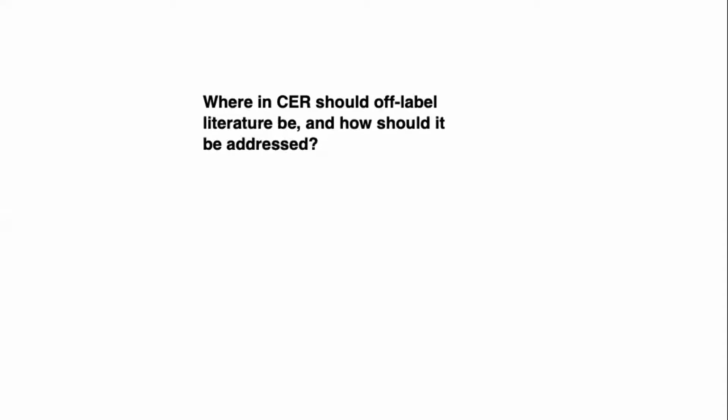Do we separate it and make a separate subsection saying off-label use of the device in the clinical literature section? Yes, we do. And we make it very clear that the data surrounding this off-label use isn't used to establish the safety and performance of the device. But off-label use does have a place in the CER as long as you're very clear that it is off-label, what it was used for, and you describe it and present that data.